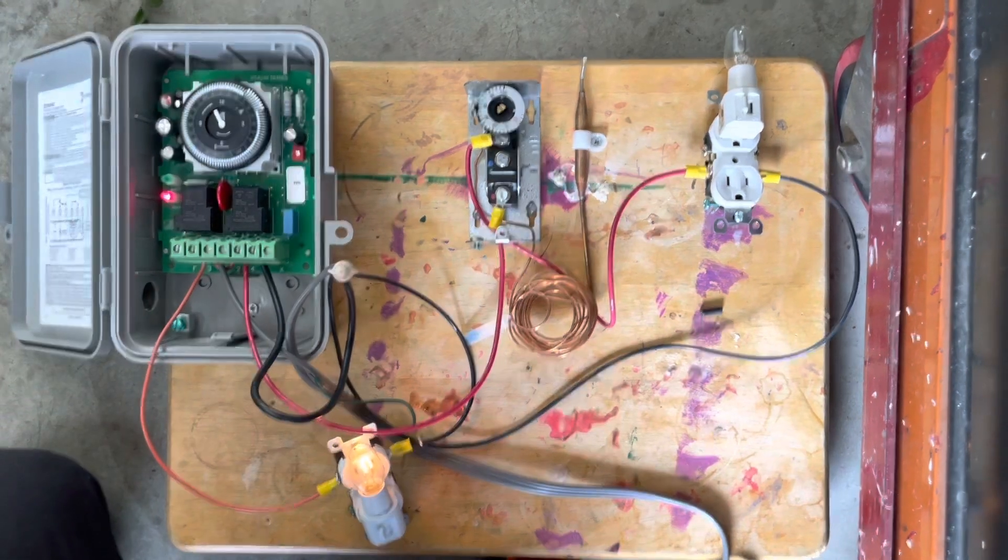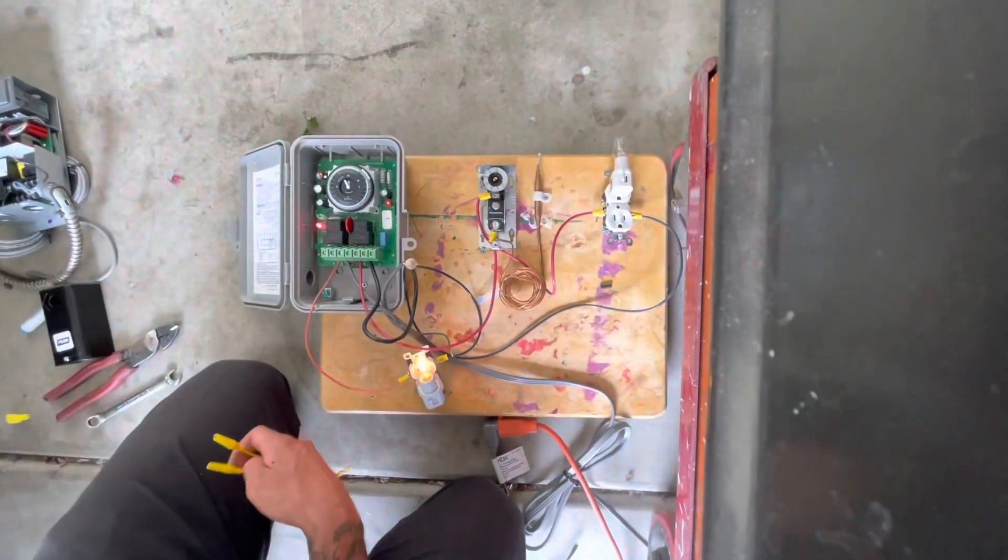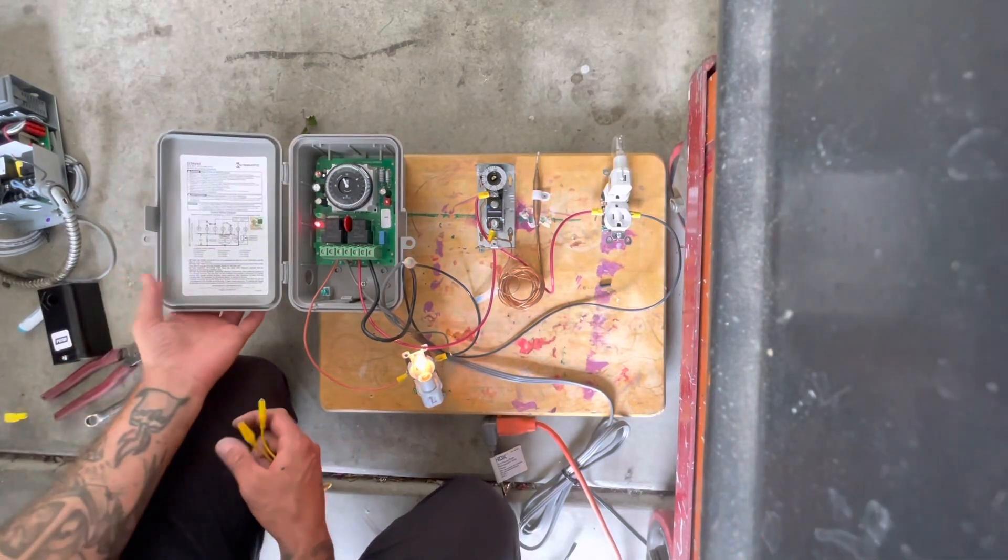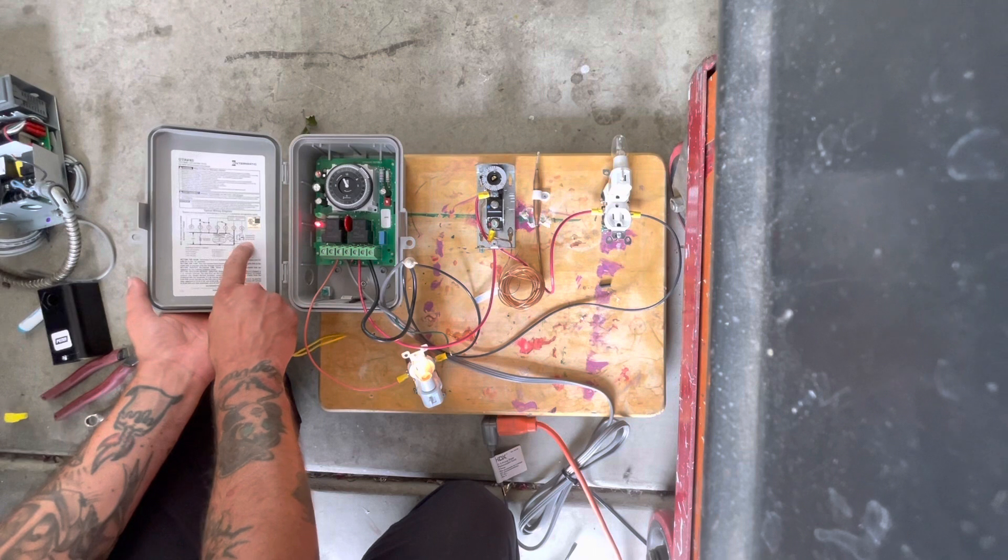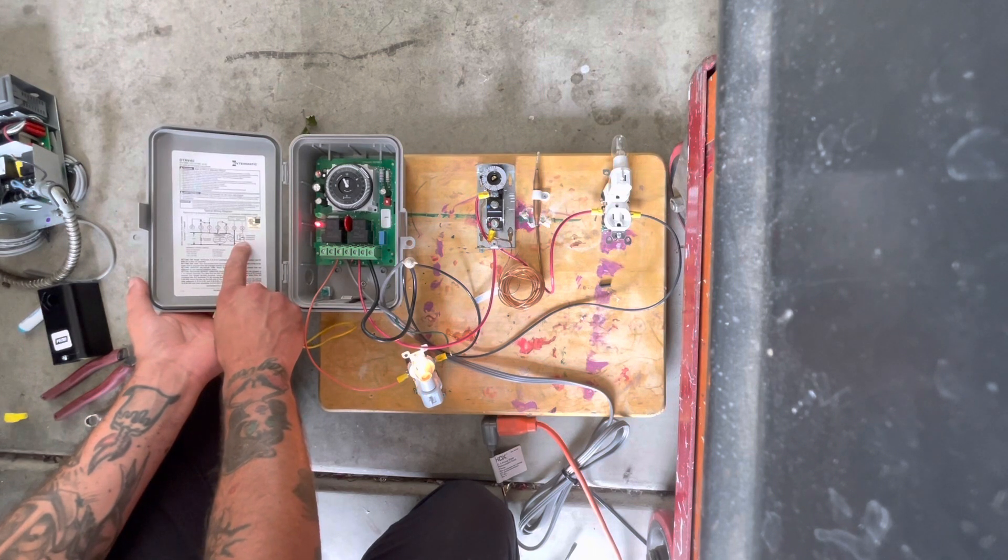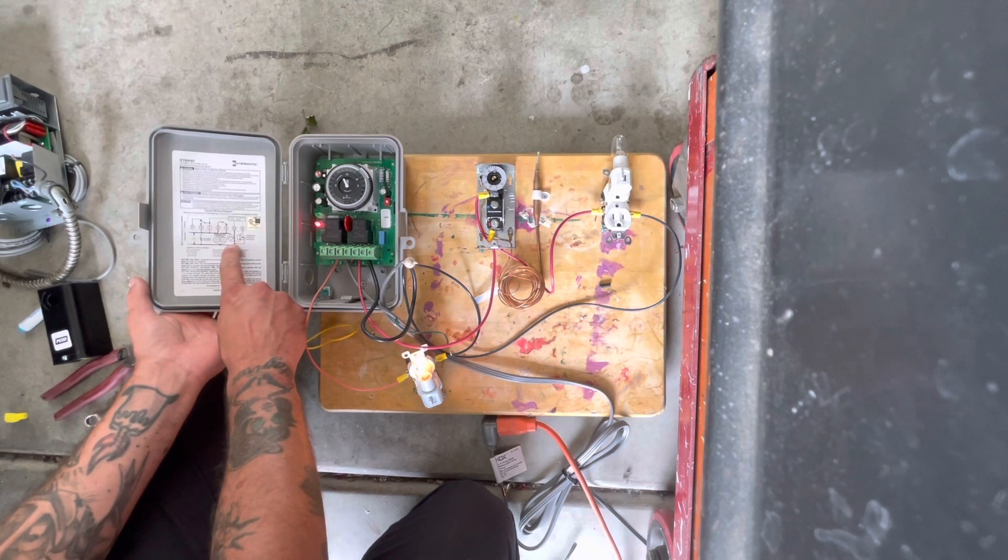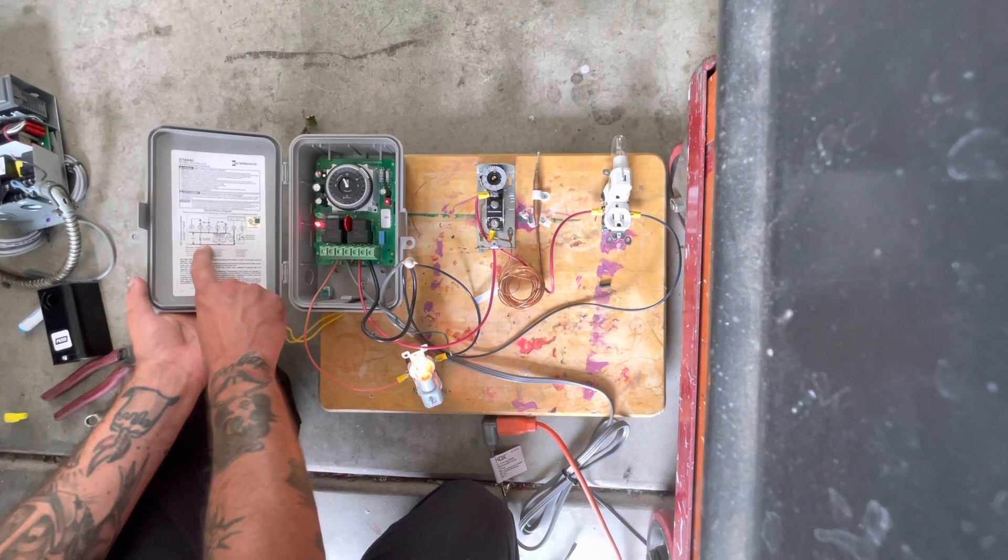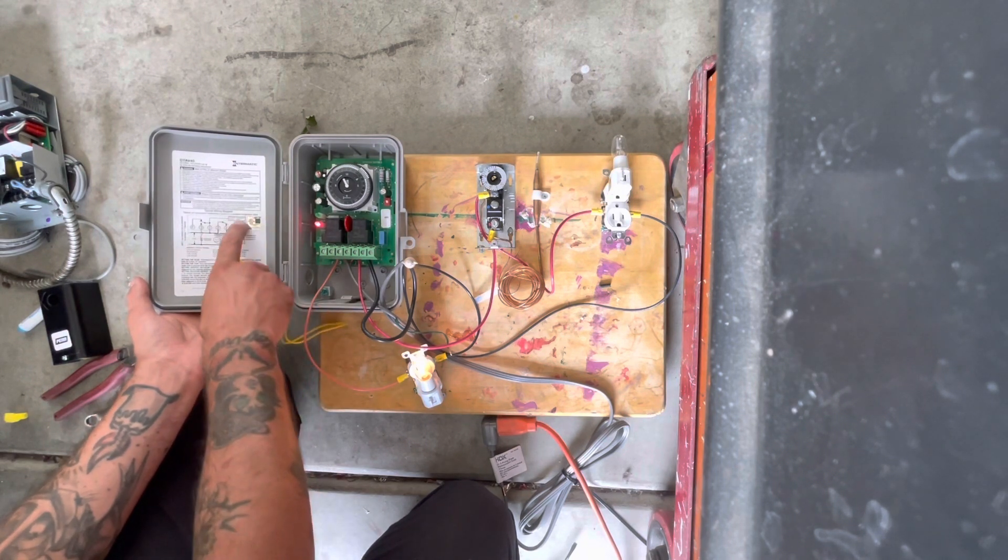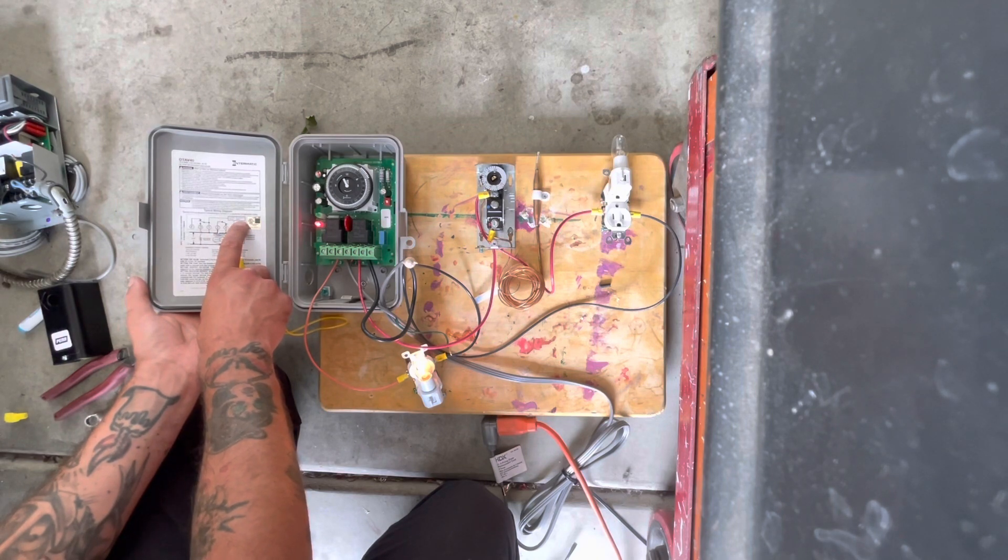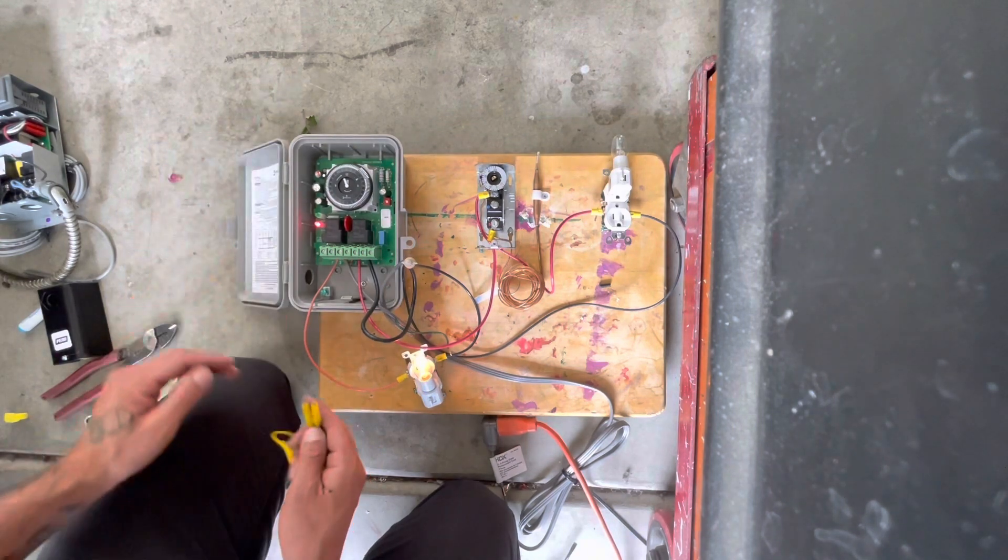All that's happening is, so on these Intermatics, the thermostat relay is just gonna switch the common power from the heater and it's gonna switch it over to X, which is gonna terminate the power. So I'll show you.